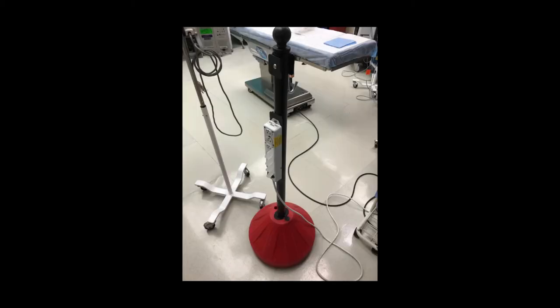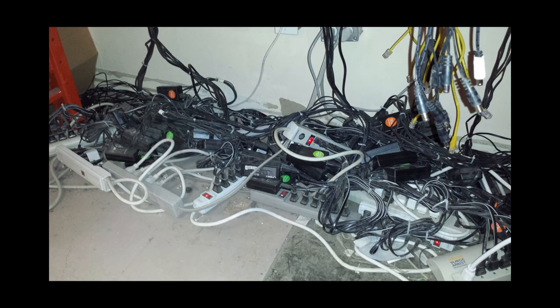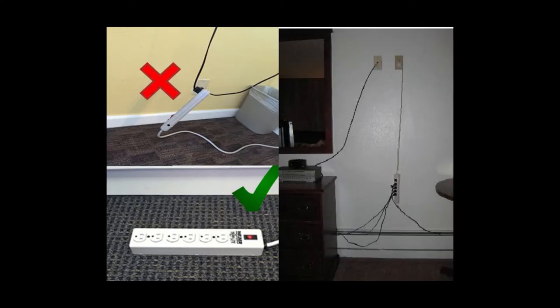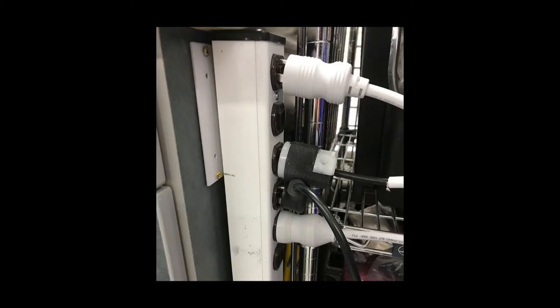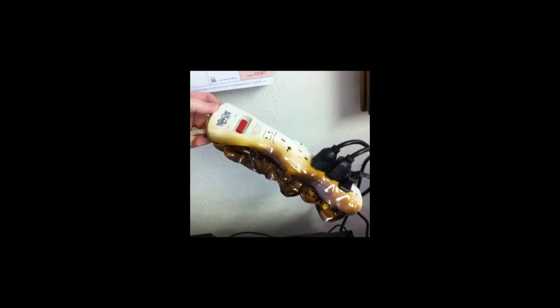If a power strip needs to be used, NFPA 101 gives the following guidance to ensure that staff uses them appropriately. 1: Prevent cords from becoming tripping hazards. 2: Connect devices so that tension is not transmitted to joints or terminals — in other words, no hanging power strips or equipment. 3: No daisy chaining of power strips. 4: Proper insertion of plugs in a receptacle so that no part of the metal prongs are exposed. 5: No overloading of power strips with high-load devices like heaters, coffee pots, or printers.